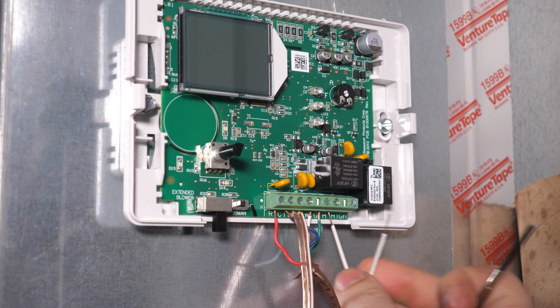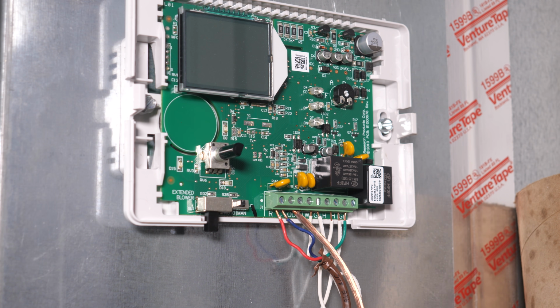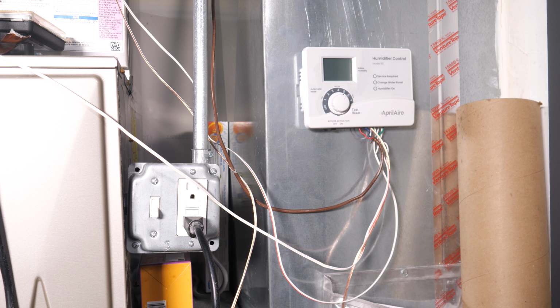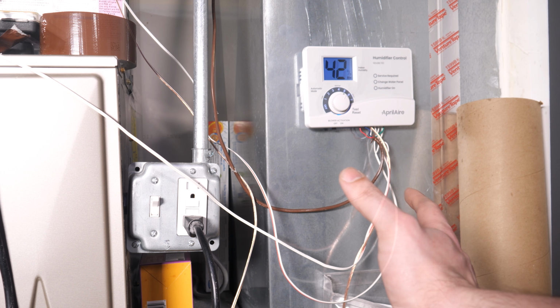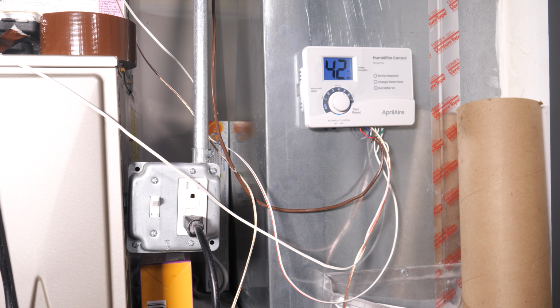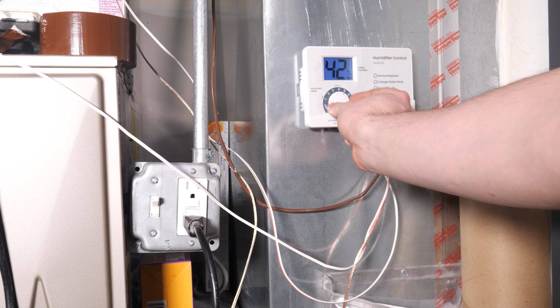This setup is what allows the humidistat to force the furnace blower on, but it will still pass a fan call from the thermostat through as normal. And finally, of course, I need to connect the humidifier's control wires to the two H terminals on the board, and the outdoor temperature sensor. With that done, all that was needed was to turn the furnace back on and test it out. Hope I didn't blow anything up. I think the outdoor temperature is high enough for it to run if I turn it to 6, but we'll see.